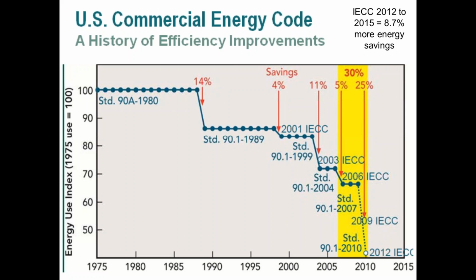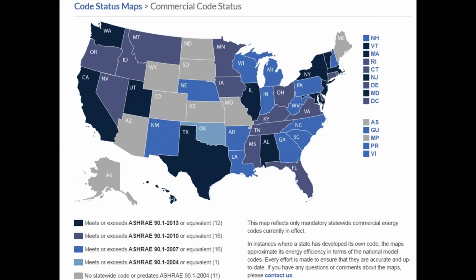Both ASHRAE 90.1 and the International Energy Conservation Code both update every 3 years. IECC updates 18 months after ASHRAE, approximately, because a lot of the information in IECC comes from ASHRAE 90.1. So we're on 90.1, 2013 version would apply to the IECC 2015. This new code that we have, I say new, it's been out for 15 months in Illinois, but this new code is about 9% more efficient than the old code. And the vast majority of that efficiency is coming from rooftop units, in my opinion, as far as HVAC is concerned. That's the biggest change.